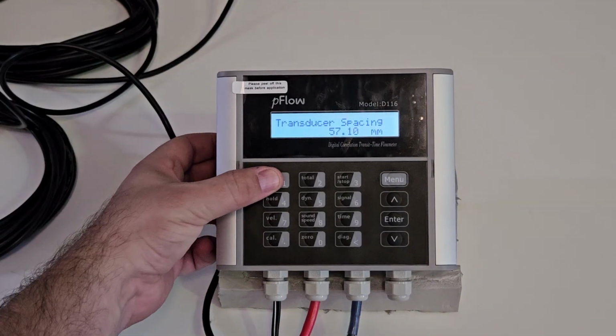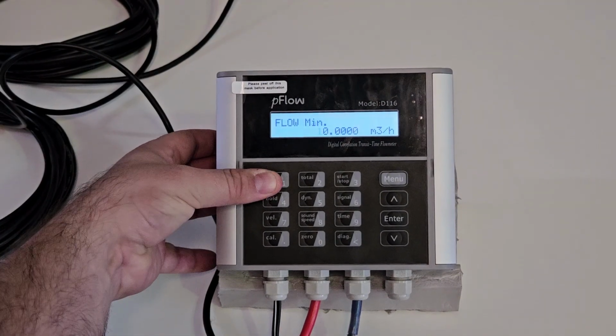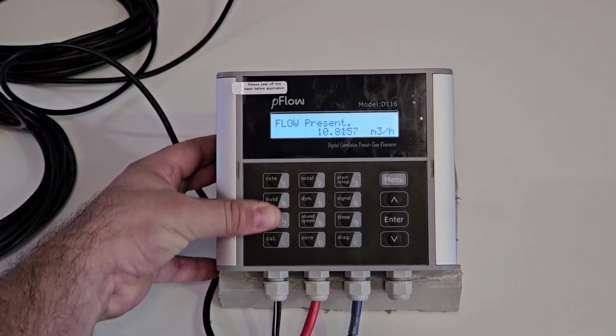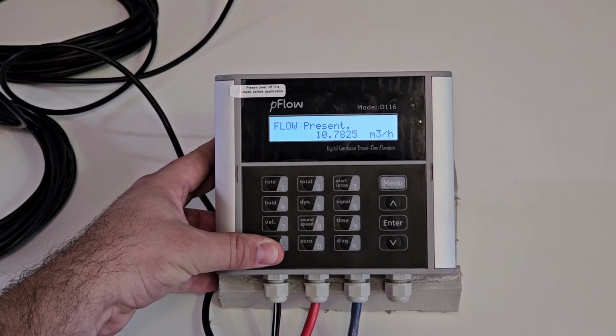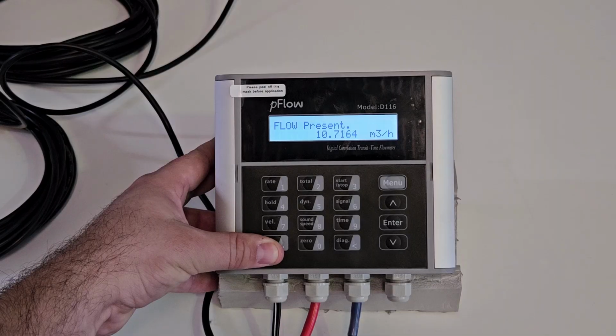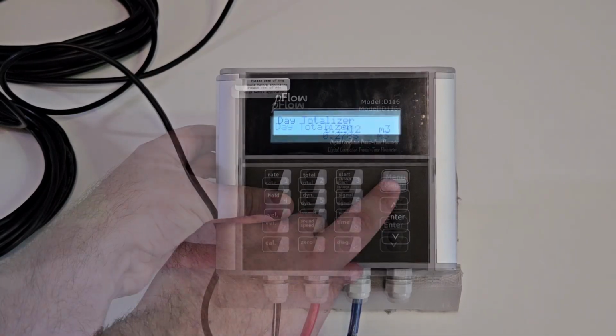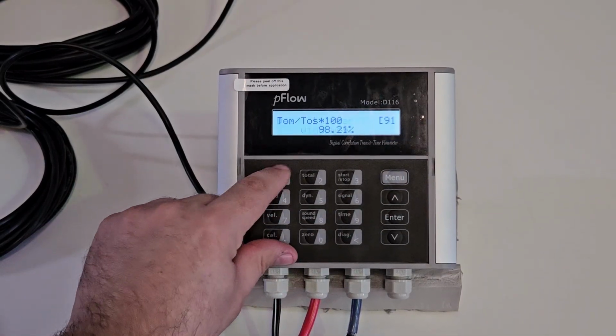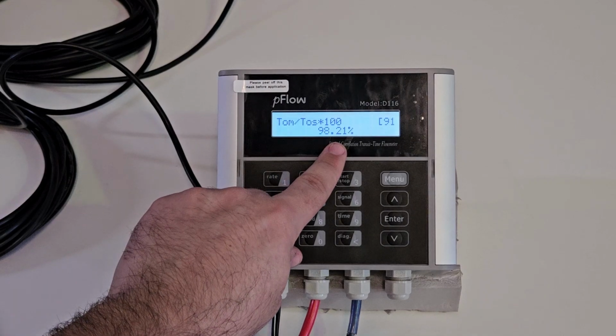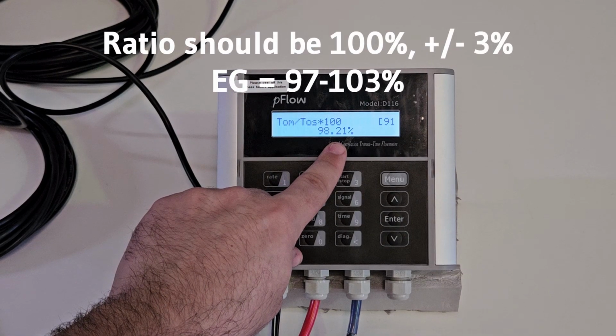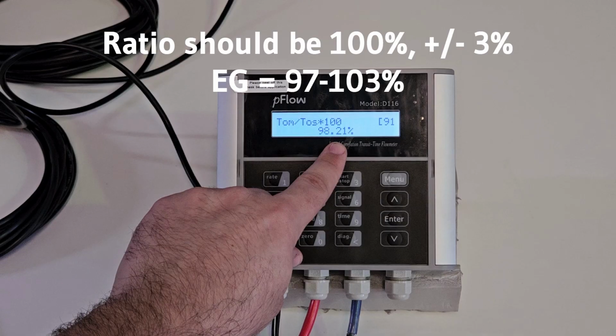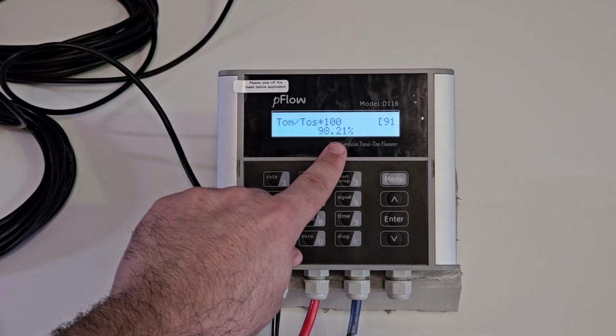If there is fluid flowing through the pipe, soon after everything is set up correctly, the meter should start measuring flow. But there are a few key values you need to check to ensure the meter is working properly. First, enter menu 91. Check the TOM-TOS ratio. This value shown is the transit time ratio. A normal expected ratio is 100% with 3% allowed variance. So between 97 and 103%.